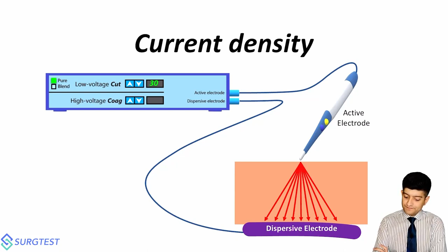What happens is when you're applying the pencil to the soft tissues, there is an extremely high current density that comes in because the tip of your cautery pen is extremely small. That entire current then spreads across the soft tissues and goes to an extremely large, wide dispersive electrode. So the current density at the dispersive electrode is much lower, even though the quantity of energy which is going across remains the same.